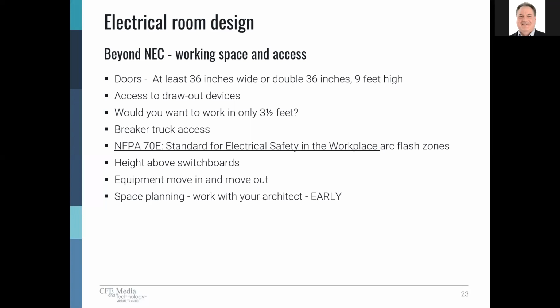The space we would want to normally have minimum is 3 foot above the gear. So look at your gear, your equipment pad, then try and add a minimum of 3 foot above your systems to allow conduits to come in and out.